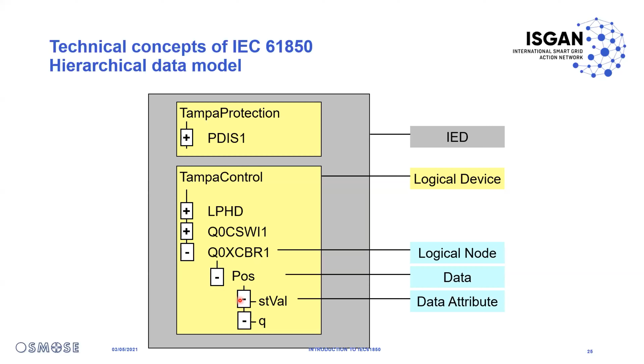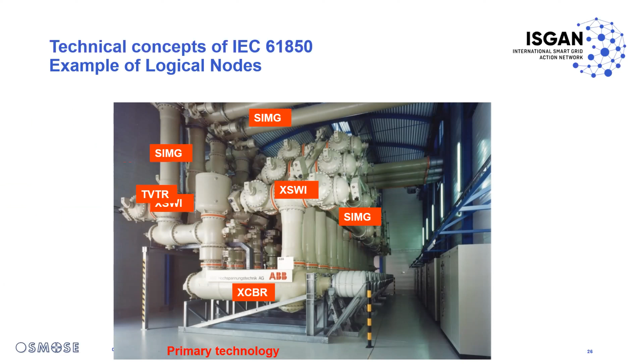IEC 61850, in the standard parts related to data models, defines a lot of these so-called logical nodes. We have here a few examples of such logical nodes as we may find them in a substation. As Gami mentioned, that was the first scope of application for 61850 — the substation automation system. So we find here logical nodes like XCBR, representing the circuit breaker as equipment, with all the information that we can gather from that equipment defined as a standardized model. We also have other elements like current transformers, switches, disconnecting switches, or earthing switches.